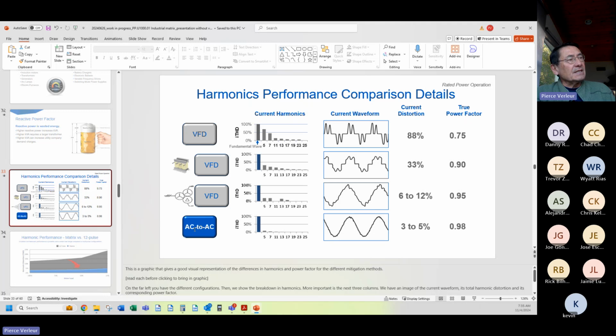Now, here is your AC to AC, and I'm going to include both active front end, AFE drives, and matrix, which is a special case of active front end, in this category. And here, you're less than 3 to 5%, but the important thing that this chart doesn't show is that this is active. As you go up and down the speed range, this stays at 3 to 5%. These other technologies do not. This is only their best, which is at full load. And here's your power factor, 0.98. And as I've said, every time we put a matrix drive in, we go from this, or this, to 0.98. And it stays at 0.98 no matter where they run the load and at what speed.